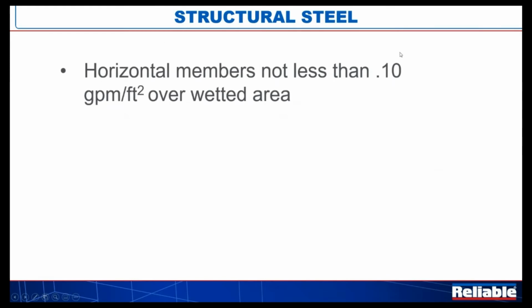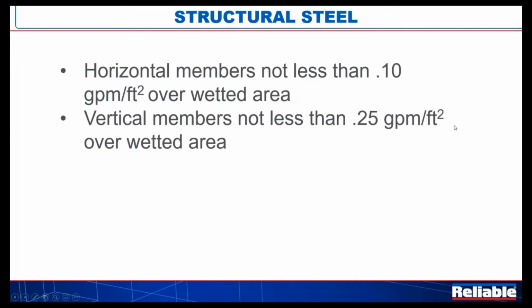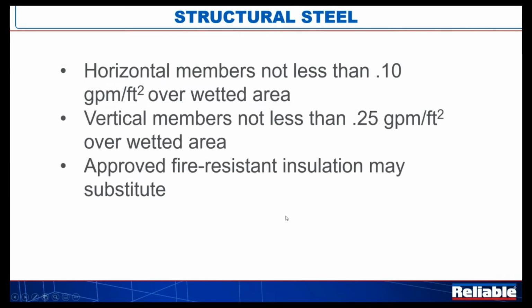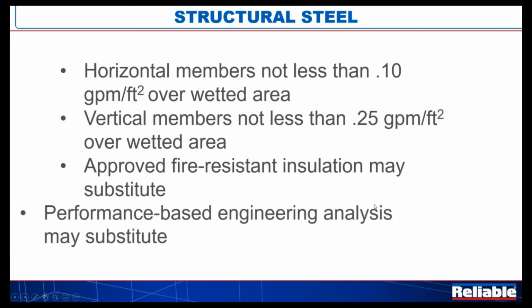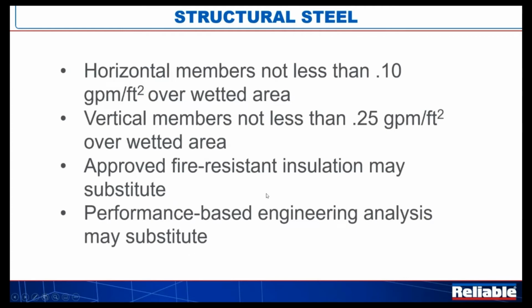Well, interesting, it leads right into structural steel. Horizontal structural members, application rate of 0.10 GPM over the wetted area. Vertical members, not less than 0.25 GPM over the wetted area. And if an approved fire-resistant insulation is applied, again, we saw that in terms of that monocoat, that can substitute with the approval of the AHJ, or some sort of performance-based engineering analysis may substitute for the spray on the steel as well.